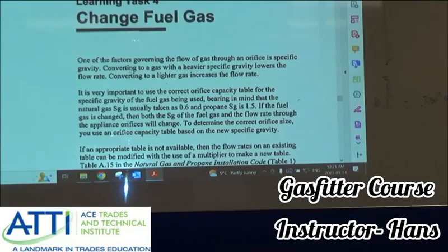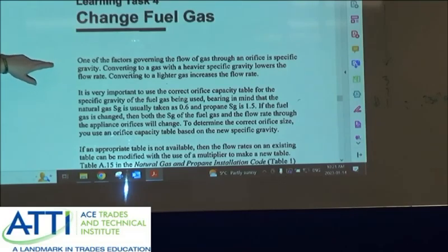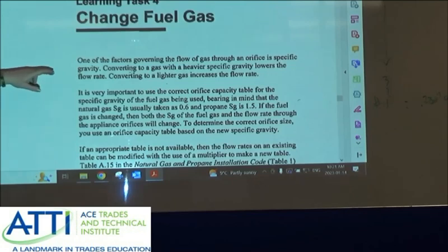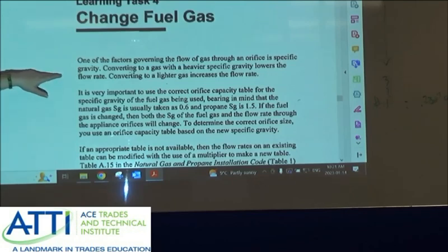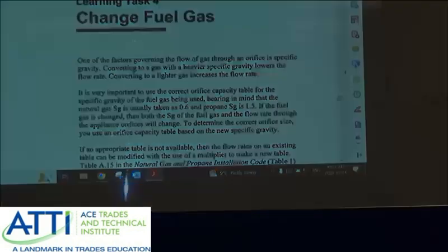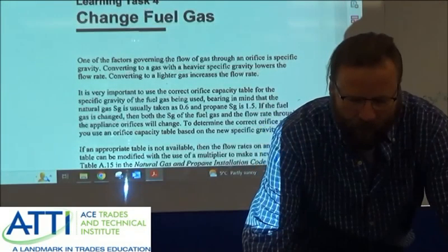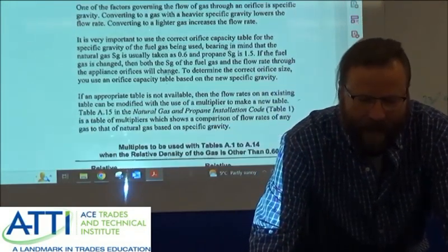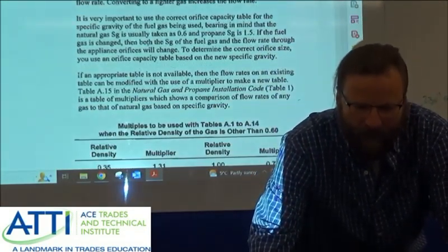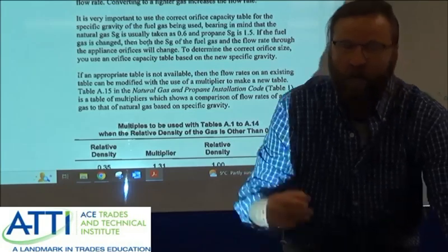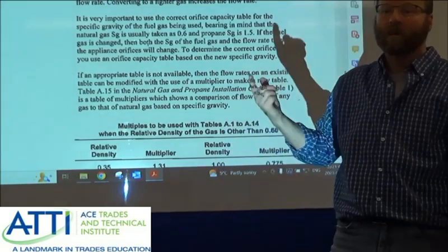Just changing fuel gas. One of the factors governing the flow of gas through an orifice is specific gravity. Converting to a gas with heavier specific gravity lowers the flow rate; converting to a lighter gas raises it. You need to use the correct orifice capacity table for the specific gravity of the fuel that's used.